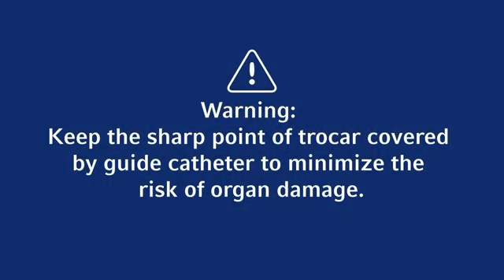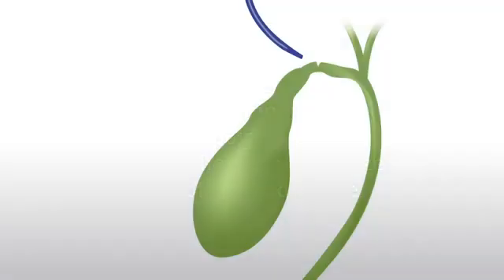Warning: keep the sharp point of trocar covered by guide catheter to minimize the risk of organ damage. Withdraw trocar completely when guide catheter is near the cystic duct. Position tip of guide catheter adjacent to cystic duct opening. Insert the balloon catheter through the guide catheter into cystic duct. Advance balloon catheter until black band proximal to balloon disappears.